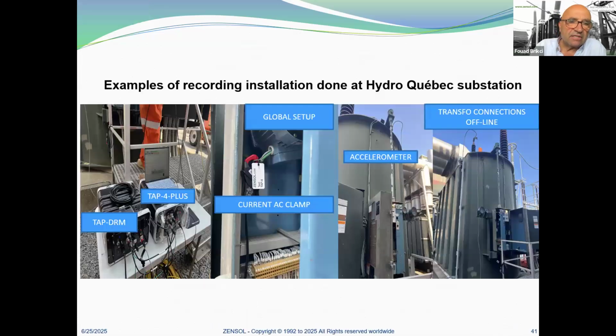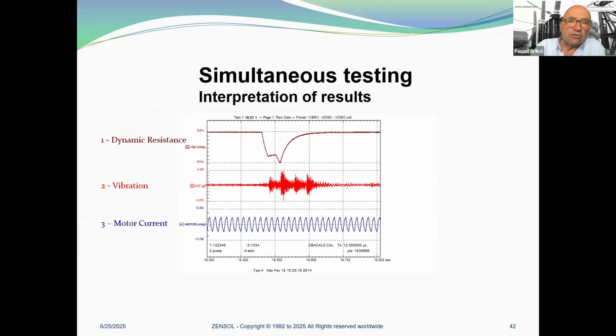Here it's the installation. You need the tap 4 plus, the DRM accessory, and here the current clamp was installed. In this example, the accelerometer and the connections to the transformer are offline, of course, because we inject DC current on the transformer. So this is the kind of result that we get. On the top, you have the dynamic resistance, the vibration, and the motor current. Here you can see the correlation between these three signals.